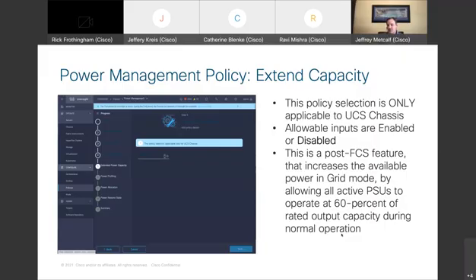So in grid mode, with 6 power supplies, you have a certain amount of available kilowatts of power. But we're seeing that in the future we may want to extend that capability. With features within the power supply and our ability to react, we can provide an effective increased capacity, extending the power supply from 2.8 kilowatts to 3.2 kilowatts—extending the available power in grid mode from 8.4 kilowatts to 9.6 kilowatts. This policy is disabled by default, but customers can enable it. This will be a post-FCS feature.